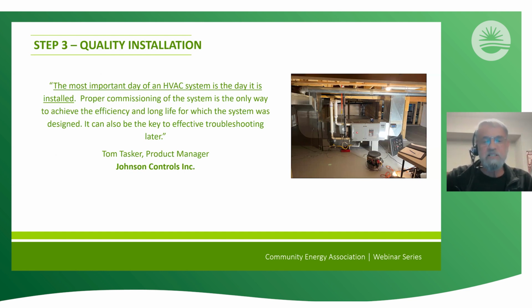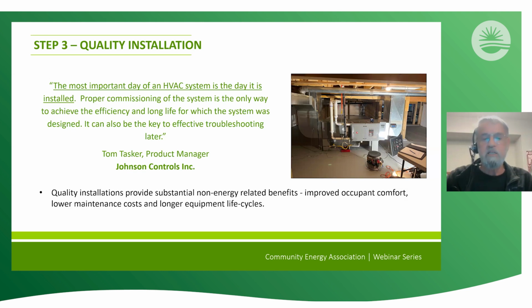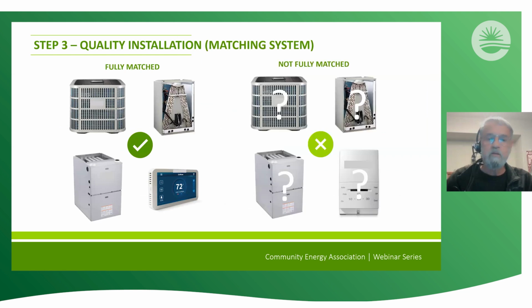So this is a quote from Tom Tasker, product manager at Johnson Controls. The most important day of an HVAC system is the day it is installed. Proper commissioning of the system is the only way to achieve the efficiency and long life for which the system was designed. It can also be the key to effective troubleshooting later. So let's expand on that. First of all, the day it's installed means you're installing something. So what are you going to install? What you want to install are systems that are made to talk to each other and work with each other. In this case, we're describing it as fully matched versus not fully matched.